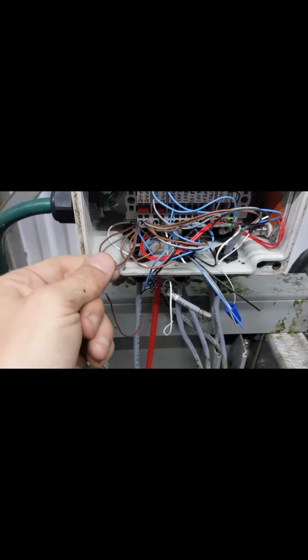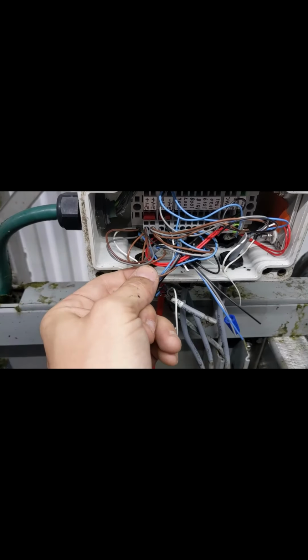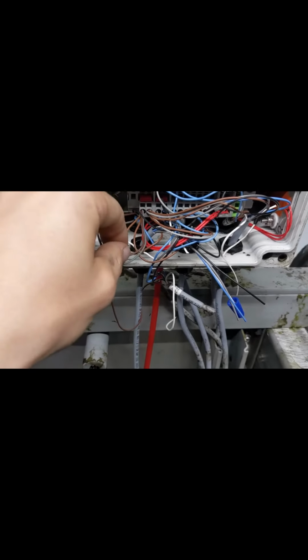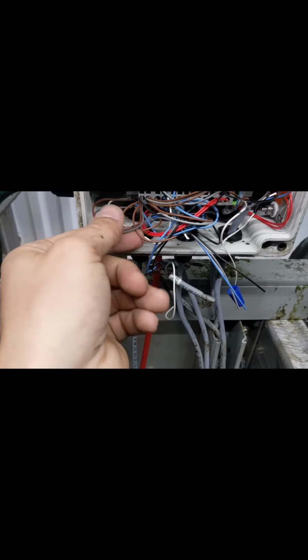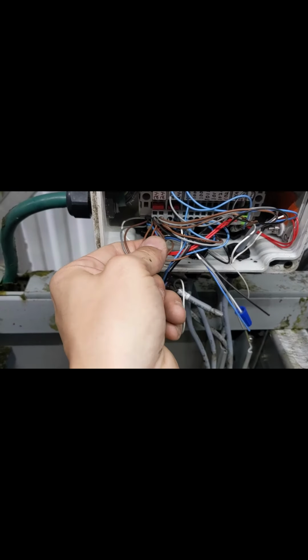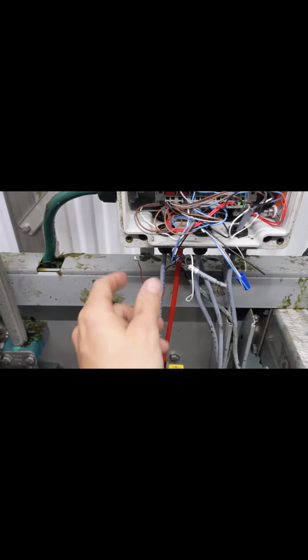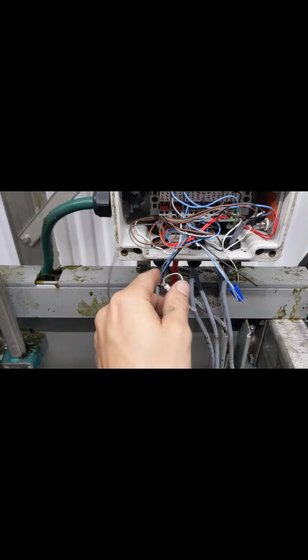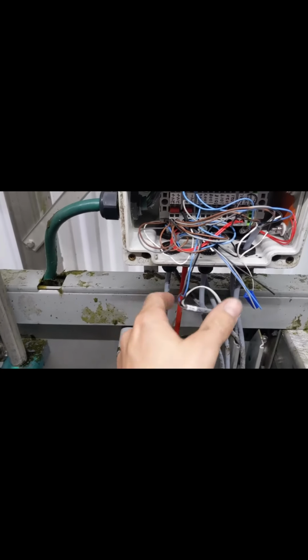Now, you don't just want to pull. Let me just get set here. You don't just want to pull on all of them together. You want to pull them individually also, and you want to make sure that every single one of these wires is in there tight. Okay. If you feel anything kind of moving, you need to take the whole thing out and do it again. It's not that big a deal. Takes you 2 seconds to do it, but it'll save you so much heartache.